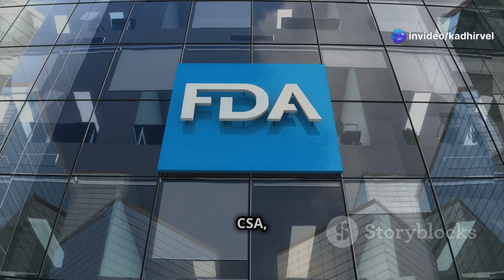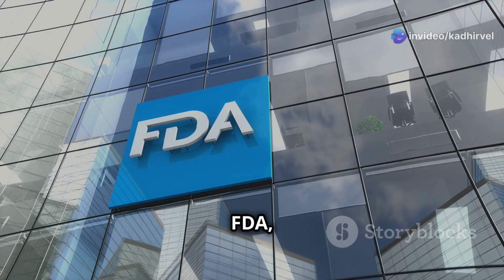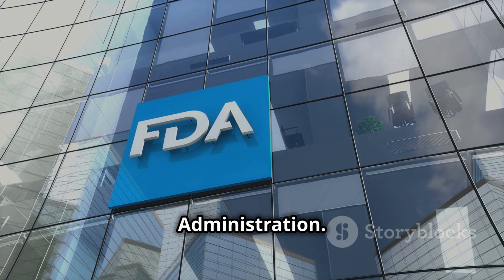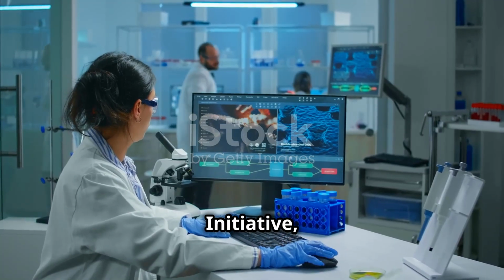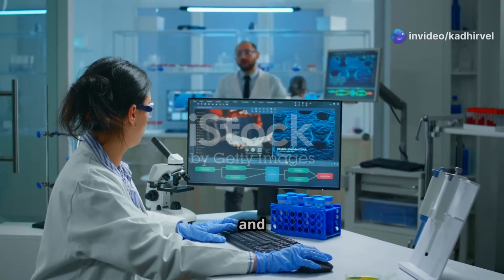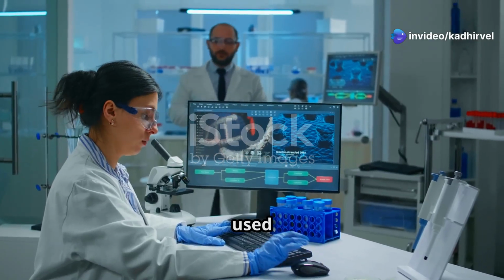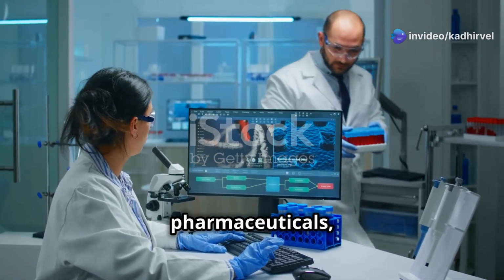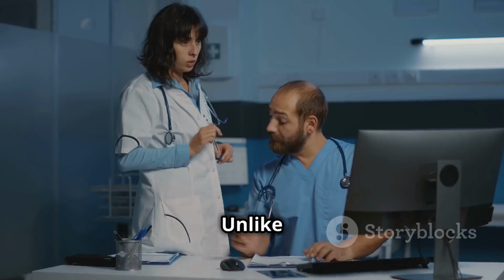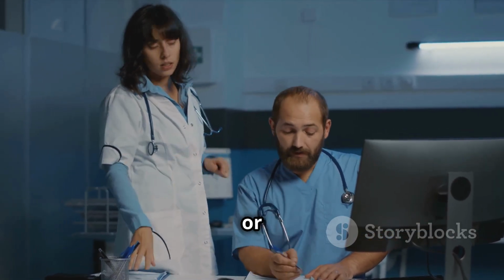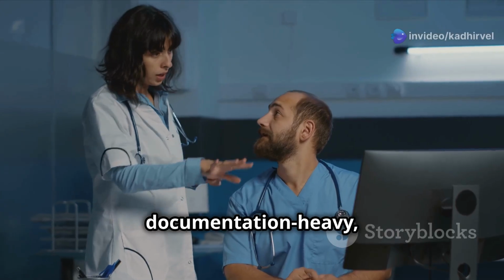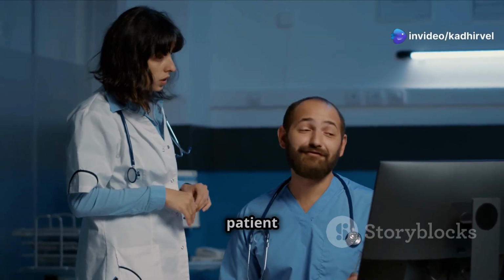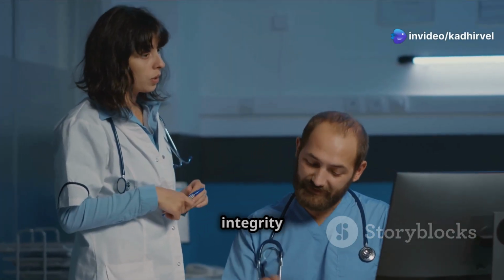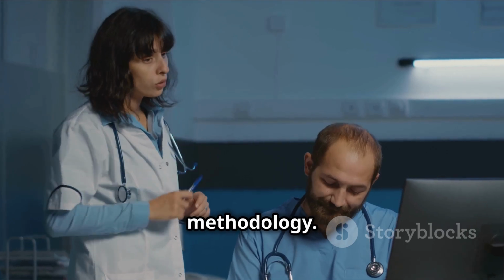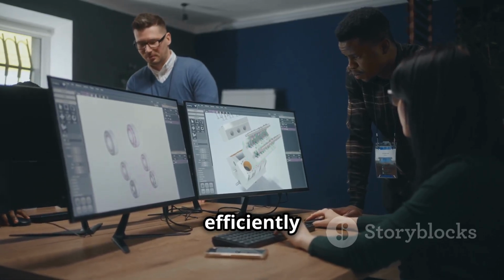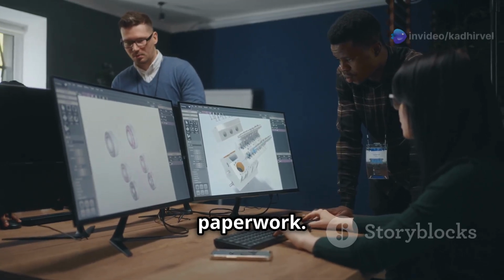Computer Software Assurance, or CSA, is a modern approach introduced by the FDA, the U.S. Food and Drug Administration. It's part of their Case for Quality initiative, aiming to improve the efficiency, flexibility, and effectiveness of validating software systems used in regulated industries like pharmaceuticals, medical devices, and biotech. Unlike the traditional computer system validation, or CSV approach, which is very documentation-heavy, CSA focuses on ensuring patient safety, product quality, and data integrity through a risk-based methodology. The goal here is to validate software more efficiently while also reducing unnecessary paperwork.